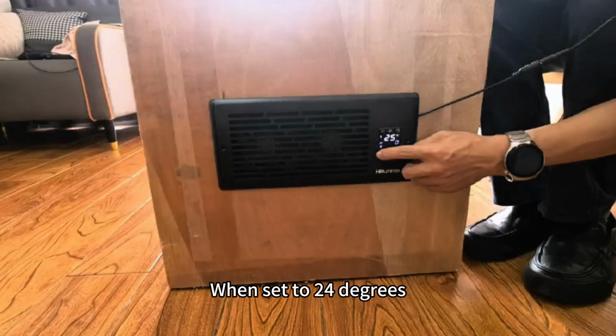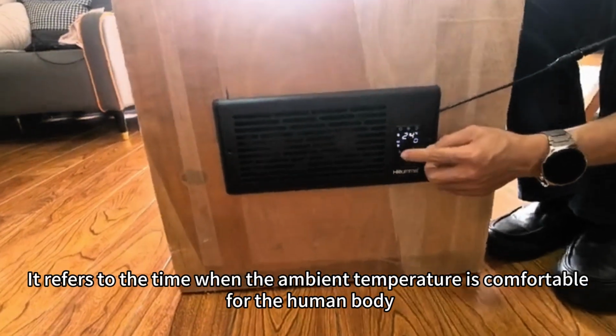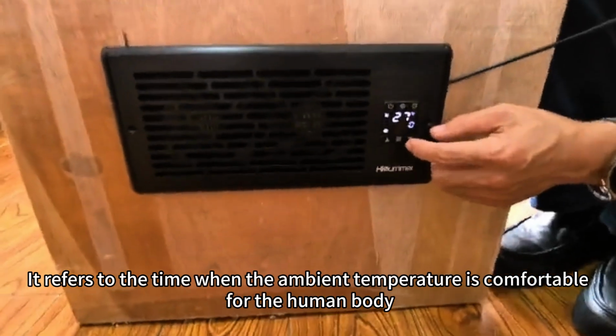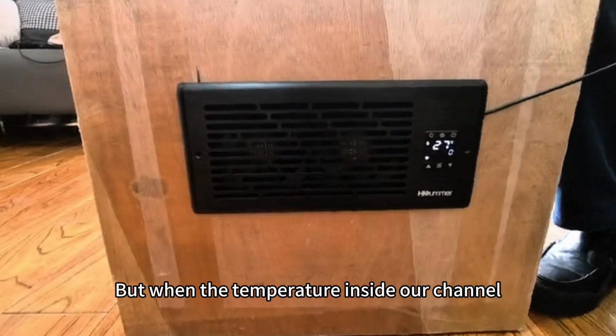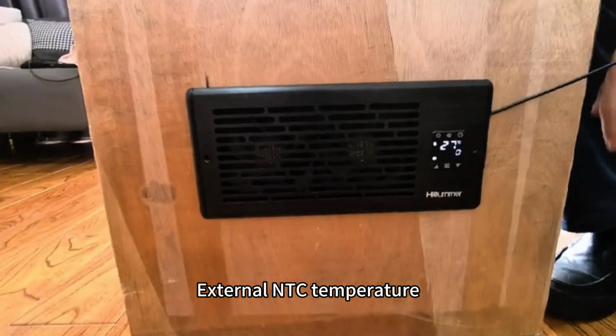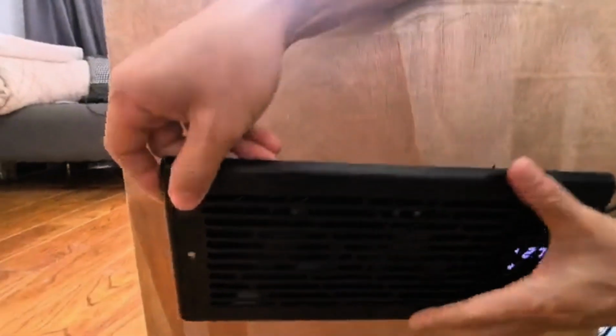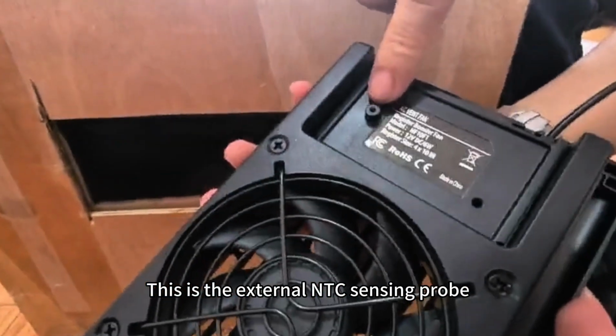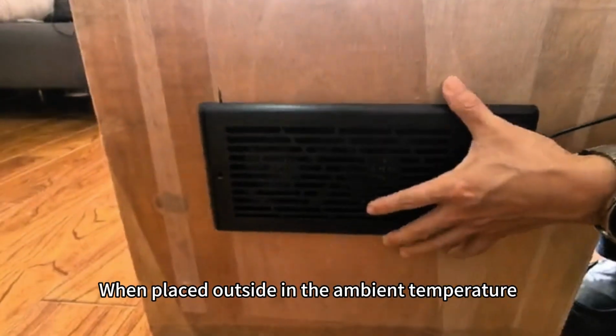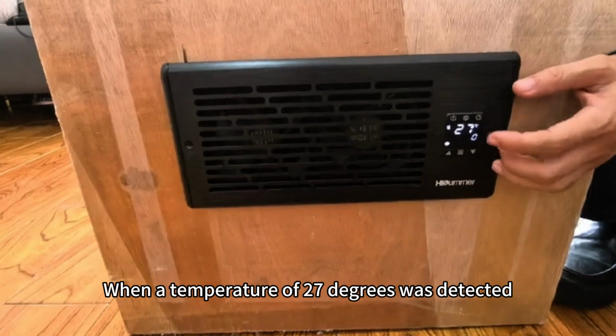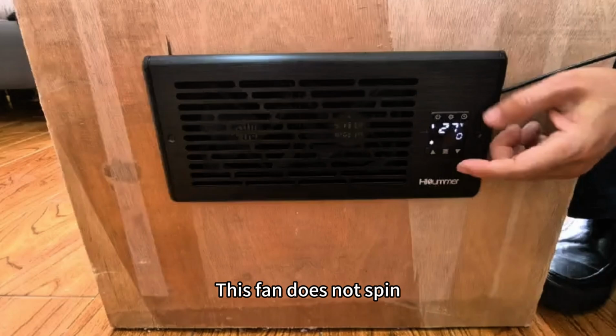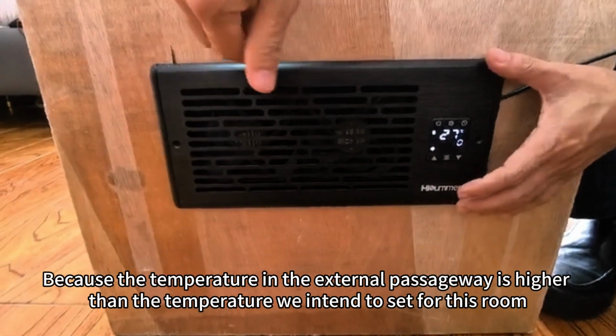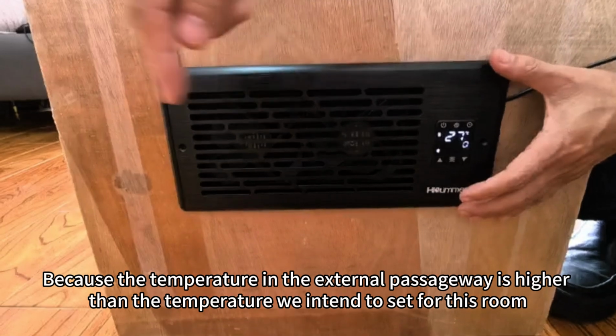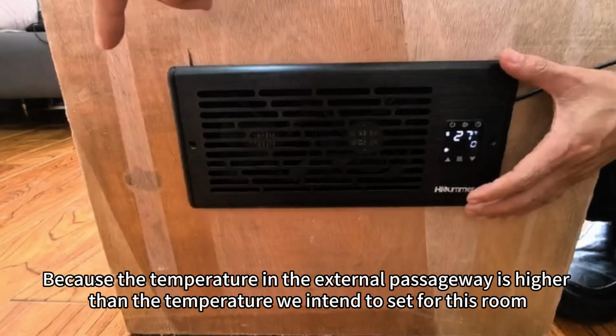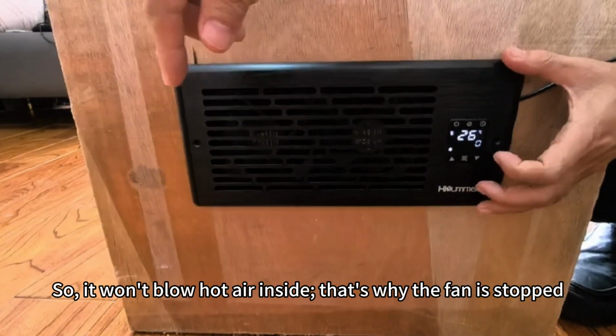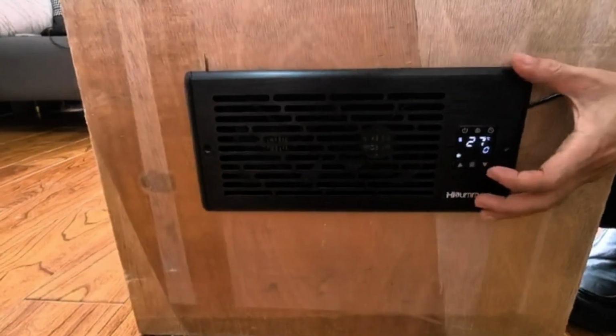When set to 24 degrees, it refers to when the ambient temperature is comfortable for the human body. But when the temperature inside our channel, the external NTC temperature... This is the external NTC sensing probe. When placed outside in the ambient temperature, when a temperature of 27 degrees was detected, this fan does not spin. Because the temperature in the external passageway is higher than the temperature we intend to set for this room, it won't blow hot air inside. That's why the fan is stopped.